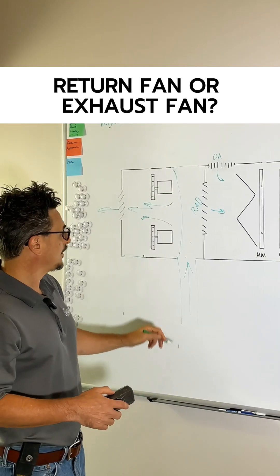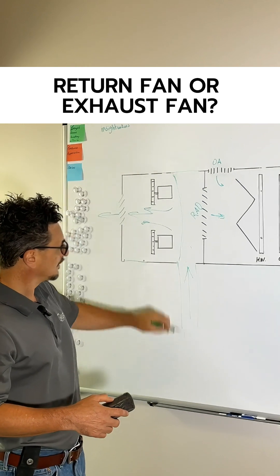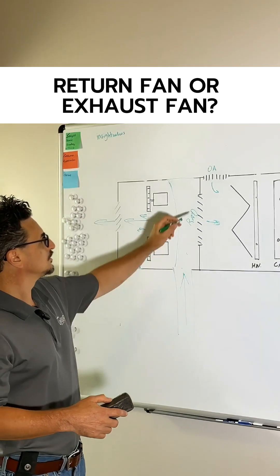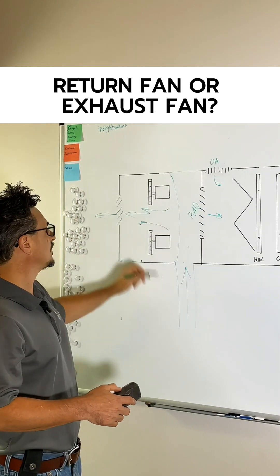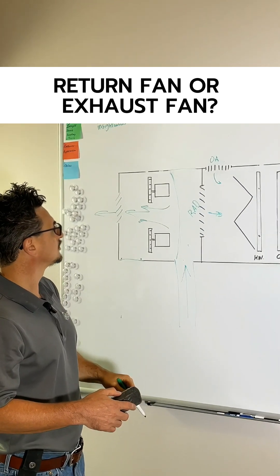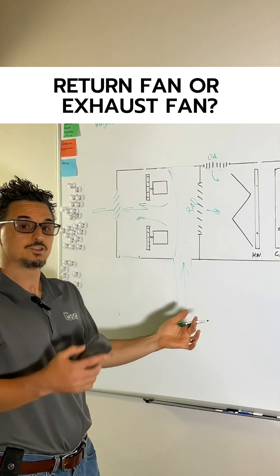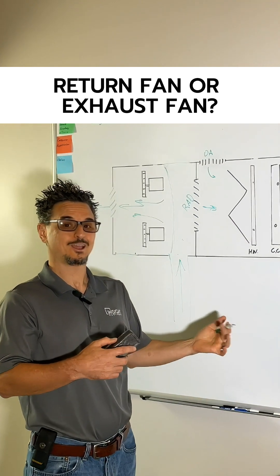And they'd also be sized to pull the air back through the return air duct, because this damper would be shut, you'd be pulling 100% outside air, and then this would be wide open. Okay, so that's the difference between the return air fans and exhaust fans.